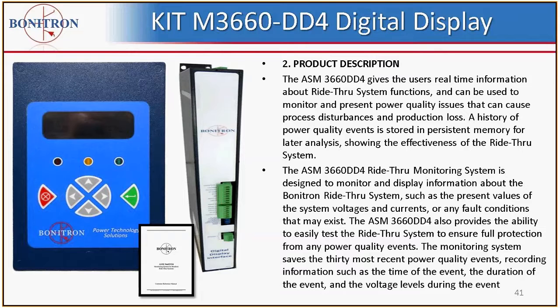The DD4 display gives the users real-time information about ride-through system functions, and can be used to monitor and present power quality issues that can cause process disturbances and production loss. The DD4 display is almost a power quality monitor, but it does not look at power factor. History of power quality events is stored in the persistent memory for later analysis, and this will show you the parameters of the ride-through event.